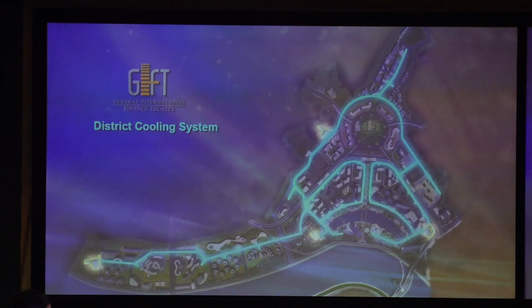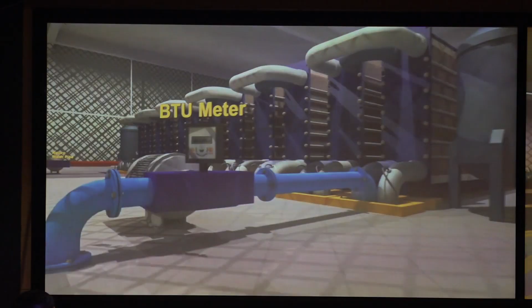Chilled water will be produced at 4.5 degrees Celsius at the DCS plant and distributed via pre-insulated pipes through trenches to energy transfer stations located at the basements of each building. BTU metering will be provided at the primary side of the energy transfer station at each building location to measure the chilled water consumption by each building.